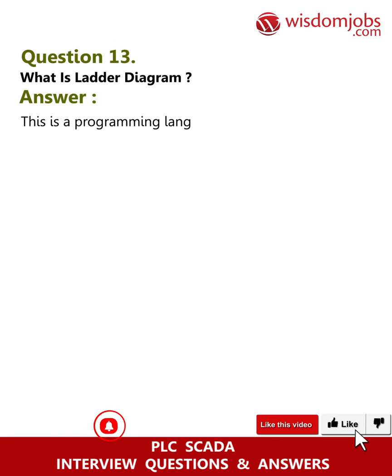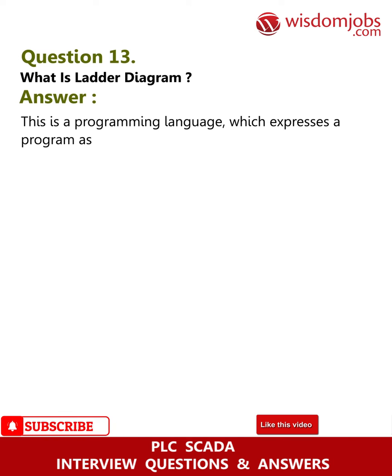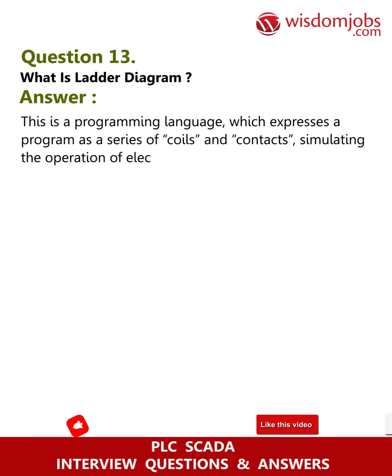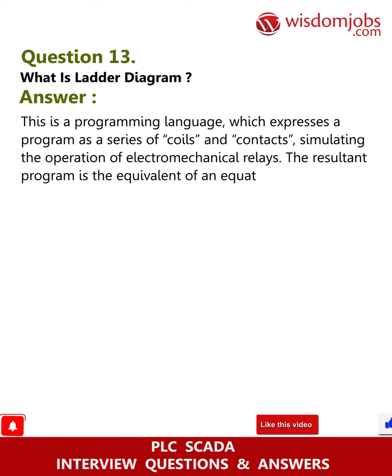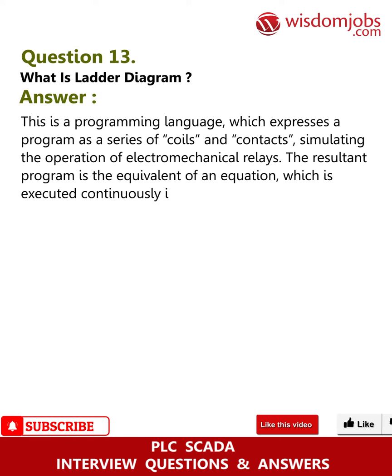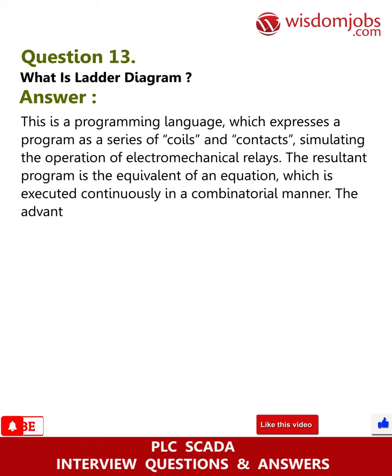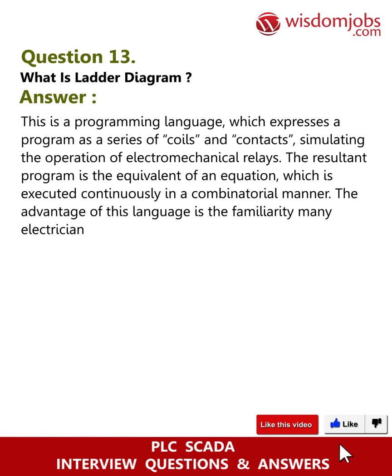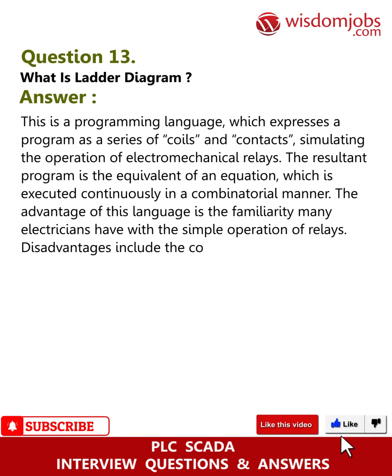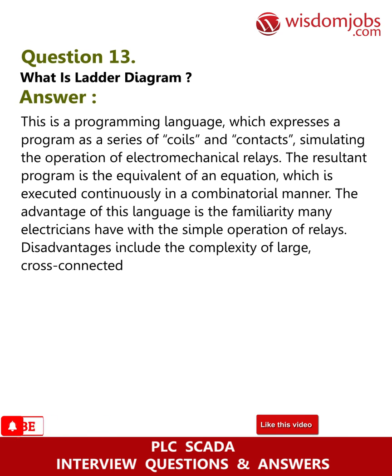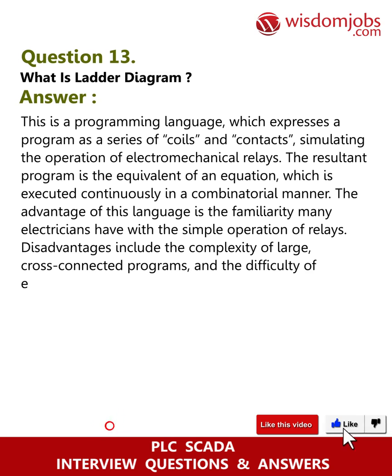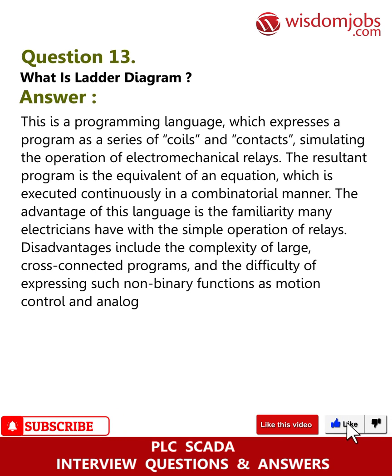Question 13: What is a ladder diagram? Answer: This is a programming language which expresses a program as a series of coils and contacts, simulating the operation of electromechanical relays. The resultant program is the equivalent of an equation executed continuously in a combinatorial manner. The advantage of this language is the familiarity many electricians have with relay operation. Disadvantages include the complexity of large cross-connected programs and the difficulty of expressing non-binary functions such as motion control and analog IO.